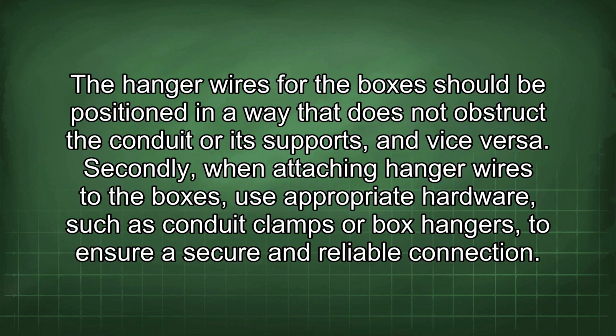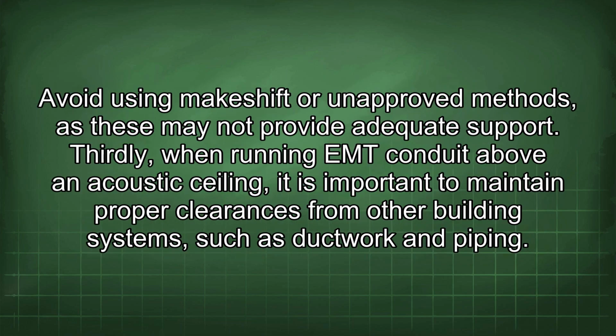The hanger wires for the boxes should be positioned in a way that does not obstruct the conduit or its supports, and vice versa. Secondly, when attaching hanger wires to the boxes, use appropriate hardware, such as conduit clamps or box hangers, to ensure a secure and reliable connection. Avoid using makeshift or unapproved methods, as these may not provide adequate support.